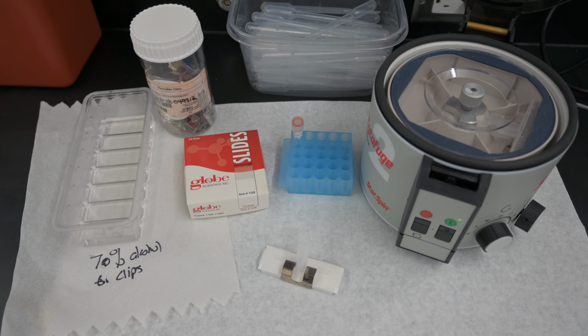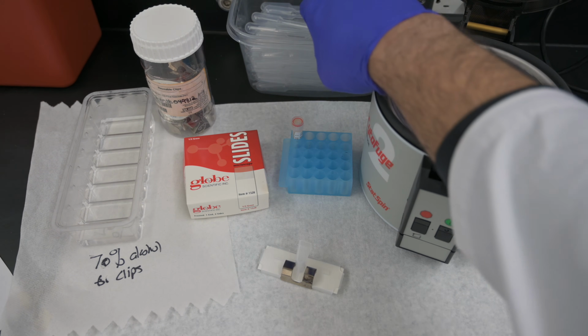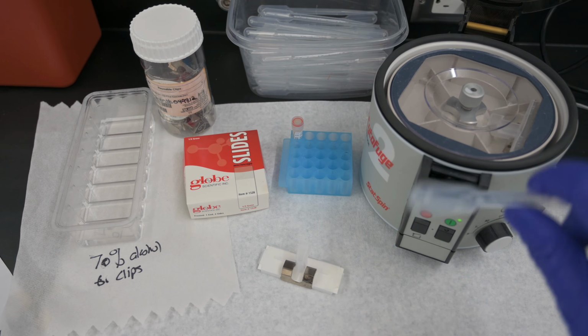Now the next step is adding our body fluid to the concentrator assembly, and this is where you're going to refer to the cell count for the sample that you've likely just performed, as well as the SOP. If that count is very low, this may require a pre-concentration step with the sample, and if the count is very high, you may need to actually dilute the sample prior to adding it.